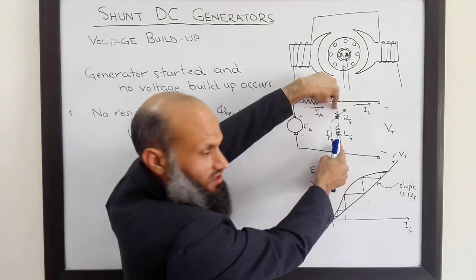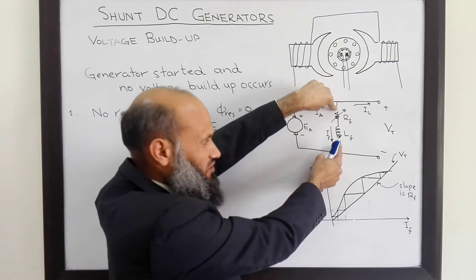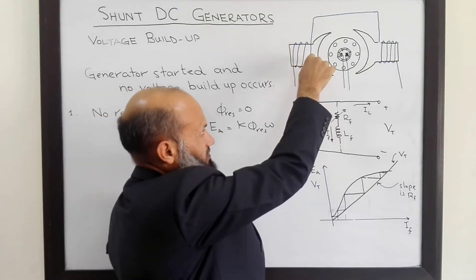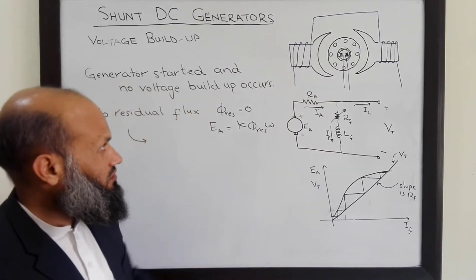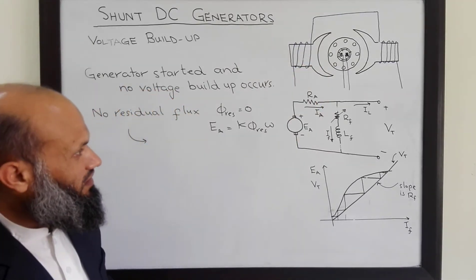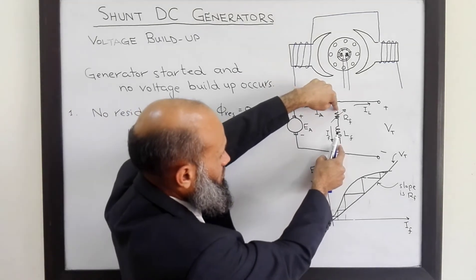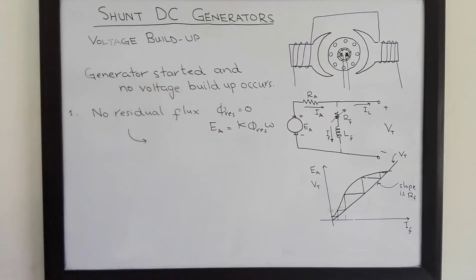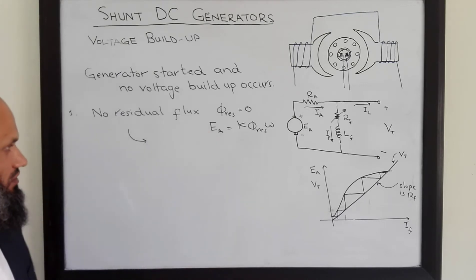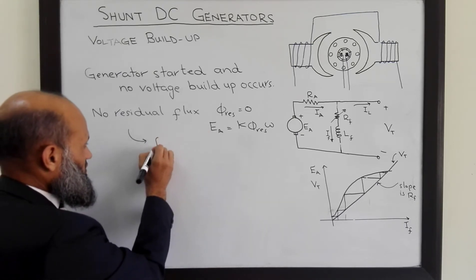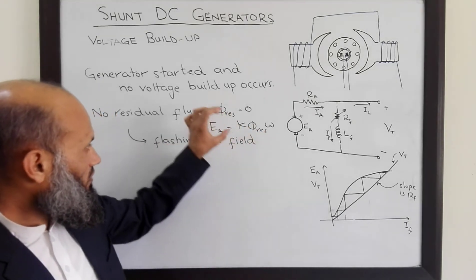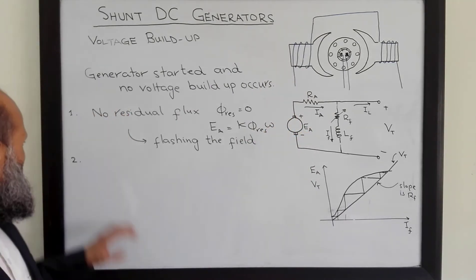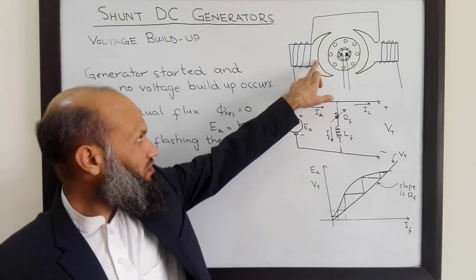The possible solution when there is no residual flux is to remove the field winding from the circuit, connect it to a separate voltage source for a brief time. Current will flow in the field windings and magnetize the electromagnets. Even when the external voltage source is removed, some residual flux will remain, and then voltage buildup will occur. This process is called flashing the field.